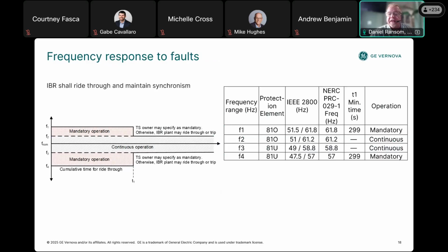The 2800-2022 and the PRC-029-1 standards state that the IBR plant shall ride through a frequency disturbance and maintain synchronism, and this is the frequency chart. The continuous operation around nominal is at plus and minus 2%. The overfrequency ride-through is plus 3% for 299 seconds, and the underfrequency ride-through is minus 5%. You can go a little bit more for 299 seconds. The transmission system operator may specify the region after 299 as mandatory. The minimum mandatory is 299. Otherwise, the IBR plant after that time may continue to ride through, or it may trip.